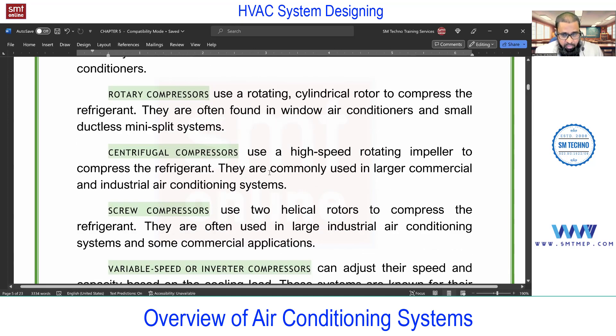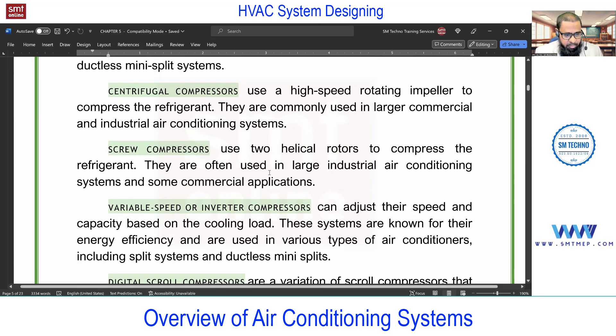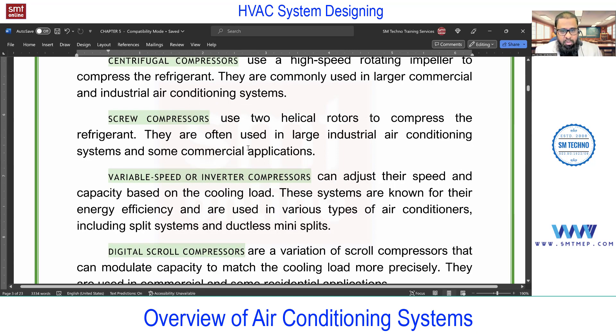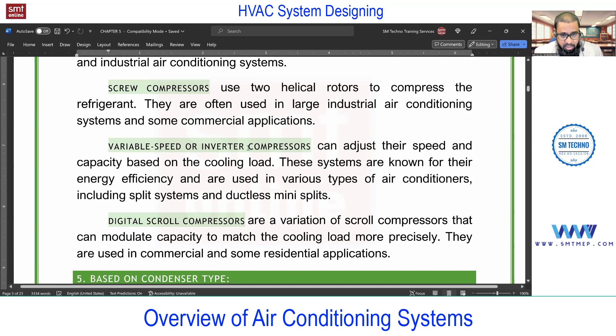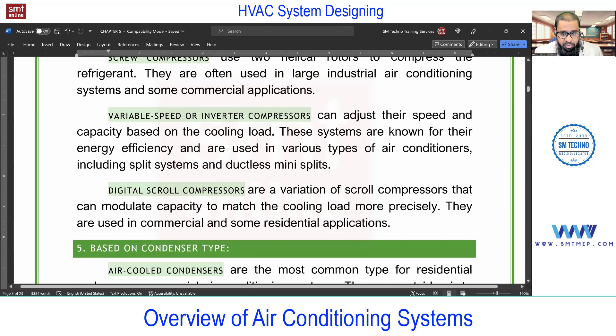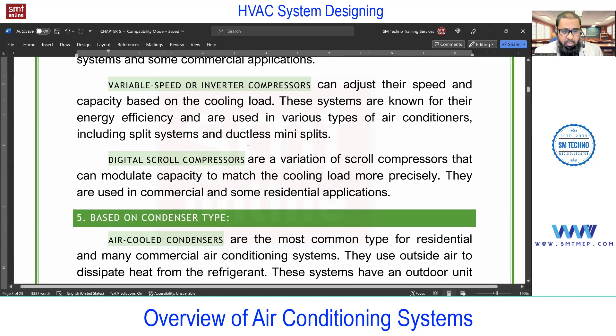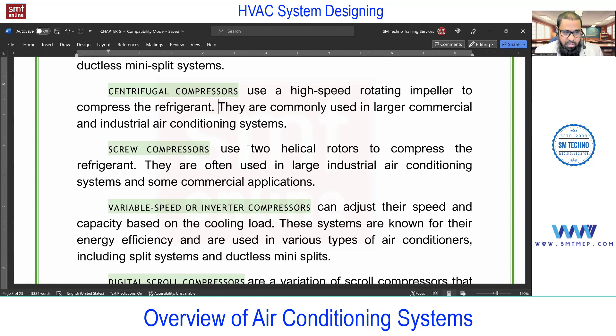Next is the centrifugal compressor — remember, this is for higher capacity units, not for small window or split units. You'll find it in large commercial systems like water-cooled chillers, up to 6000 TR. Next is the screw compressor, which has two screws; refrigerant is supplied between the rotating screws for compression. Then we have variable speed compressors — even split systems now use inverter-type variable speed compressors for efficiency. Finally, digital scroll compressors reduce power consumption further and are more precise than normal compressors. Systems can thus be classified as scroll compressor chillers, screw compressor chillers, reciprocating compressor chillers, etc.